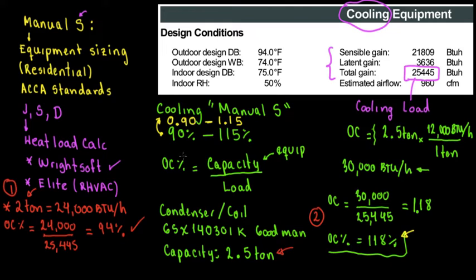So, the answer is the following. I personally rather size my equipment not considering the 90%. If I was going to do this my percentage would be personally 105% to 115% even 120%. So, this is undersized for me, 94% which is lower than even you can see here your house is asking you need 25,000 BTUs per hour but you're giving him less, 24,000. So, in this case this is lower. Anything about 100% is good for me but for me it's better to be a little bit more, have a buffer.